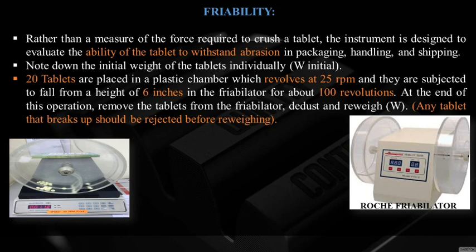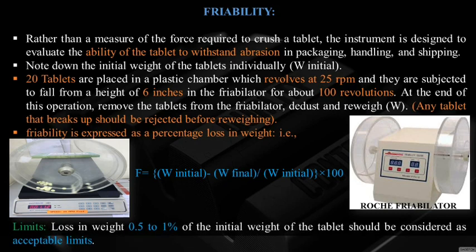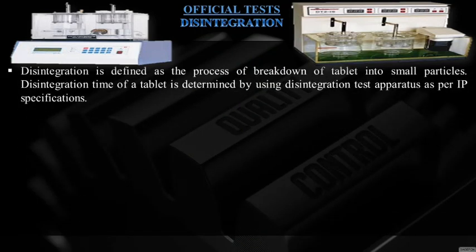At the end of the operation, remove the tablets from the friabilator, dust them, and re-weigh. Any tablet that breaks up should be rejected before re-weighing. Friability is expressed as a percentage loss in weight: (W-initial − W-final) / W-initial × 100. The acceptable limit is a loss of 0.5 to 1% of the initial weight of the tablet.